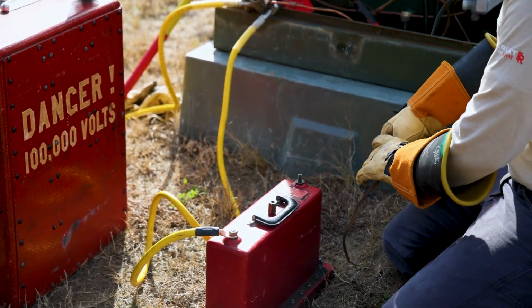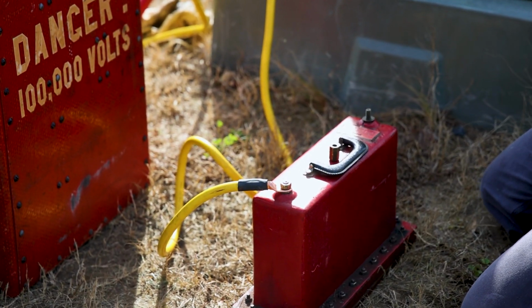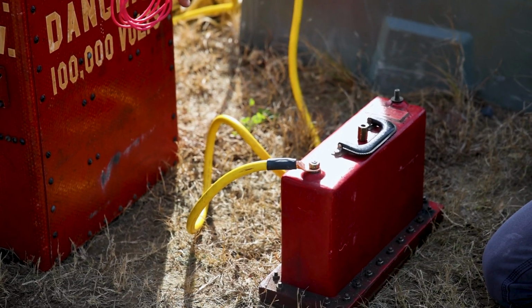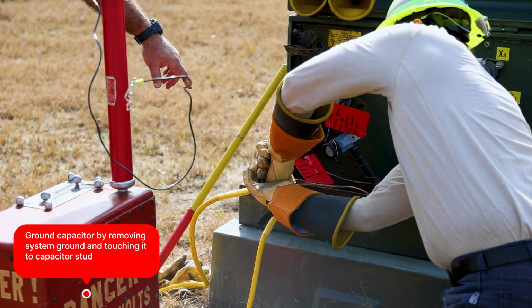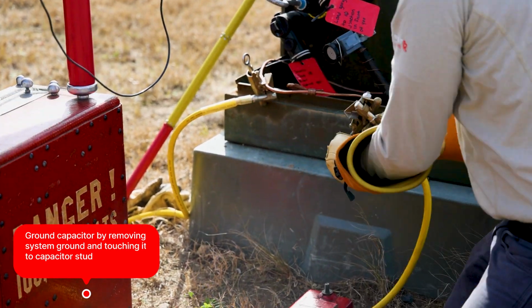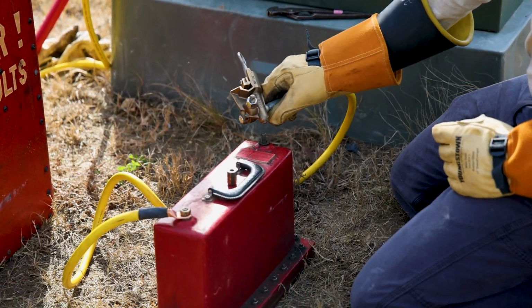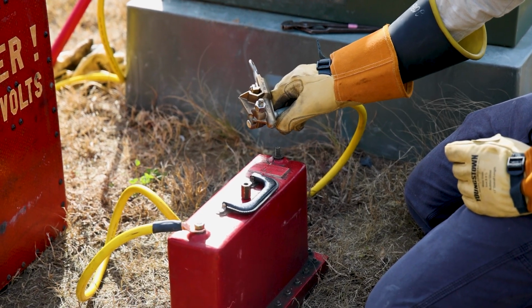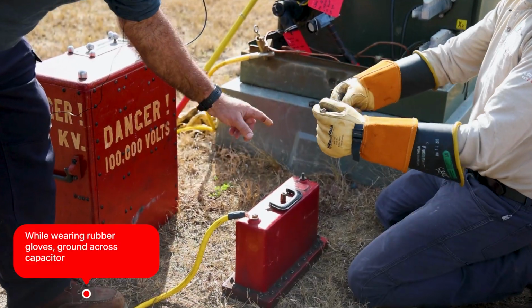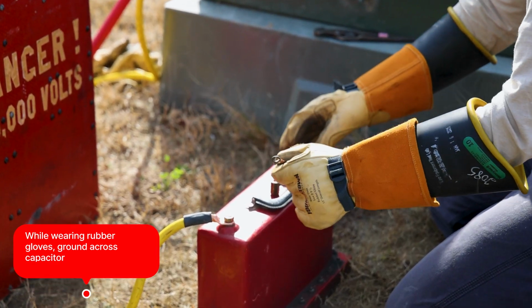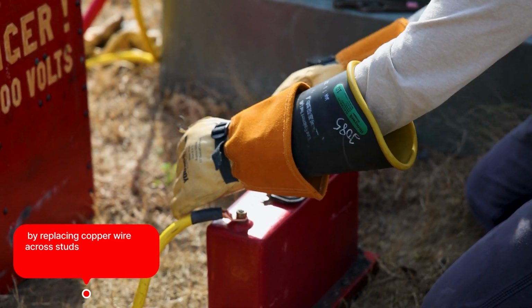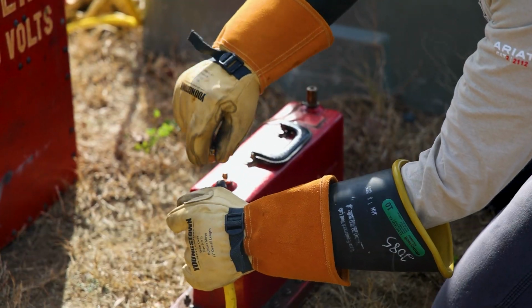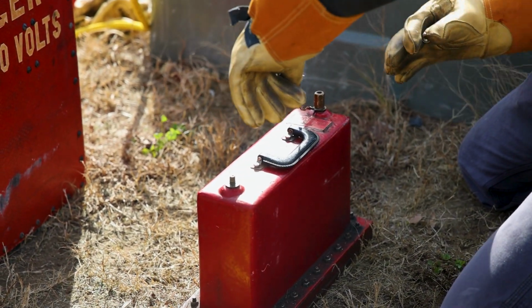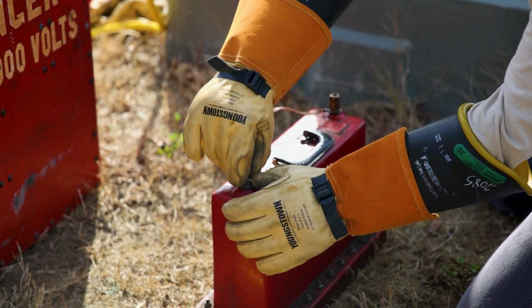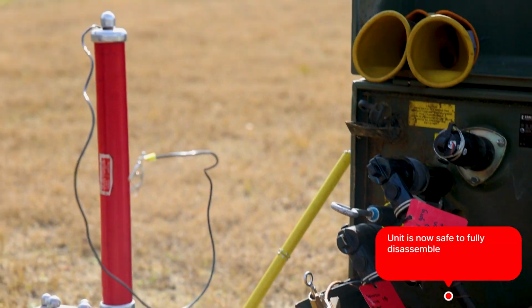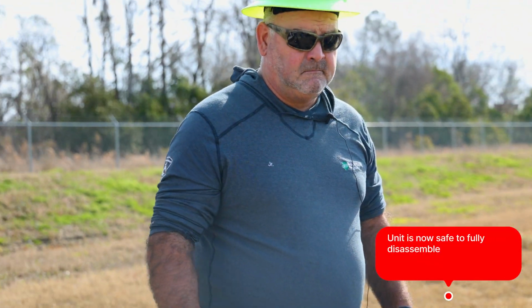When you're messing with this capacitor, you need to ground it. So the best thing to do, since you have one side ground already hooked up to it, is take the ground loose on your system ground and touch it to the other stud on your capacitor. Now that he's done that, still with your rubber gloves on, you need to ground across your capacitor with this copper wire. Once it's grounded, it's safe to pick it up and load it back up.